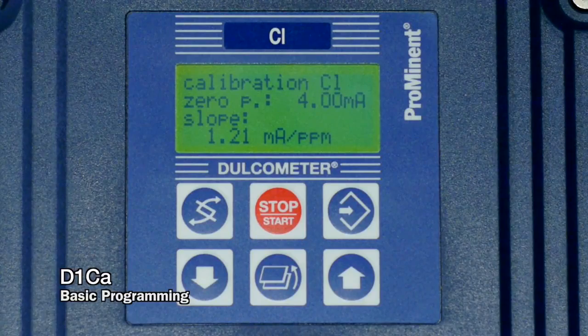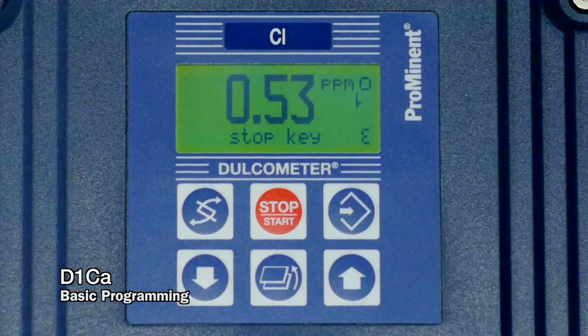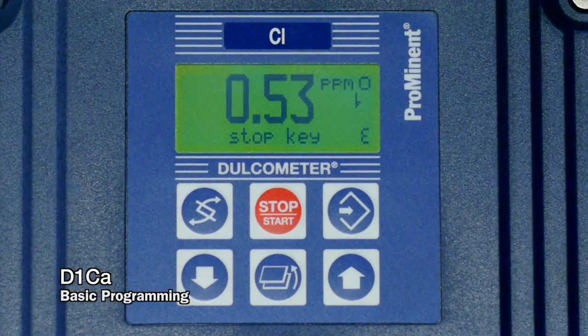In that case, most commonly, you have to change your membrane cap and electrolyte again and allow it time to energize that electrolyte. But here we have a good slope, so we can hit the enter button and you'll see we go back to the main display. Those are the basics for setting up the programming on your D1CA. It's very similar, although we're displaying a chlorine unit here. It's very similar for the other parameters that are available on amperometric sensors as well.